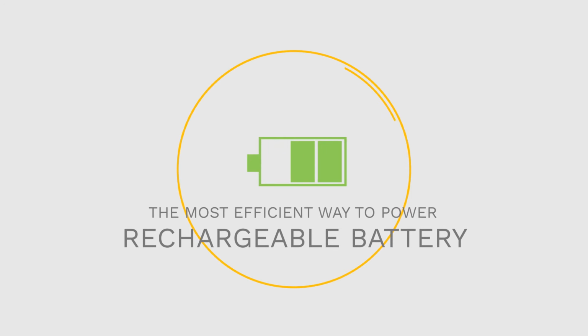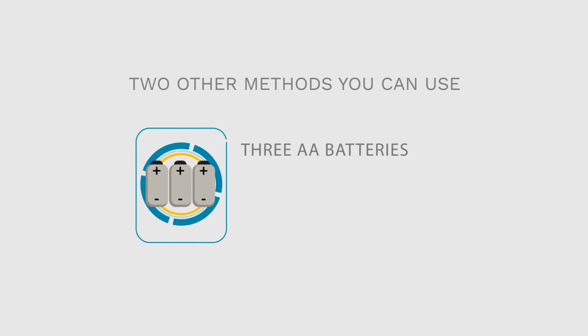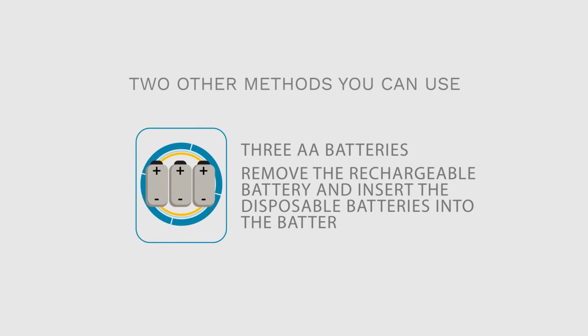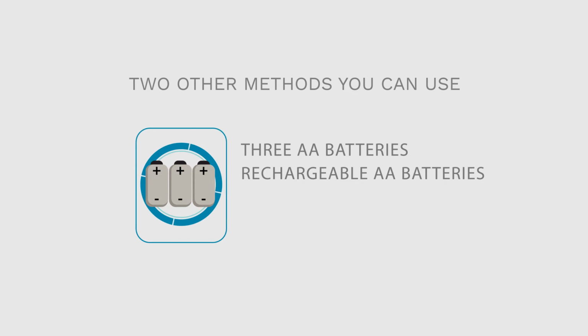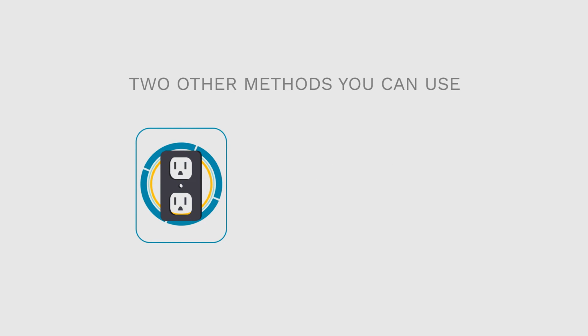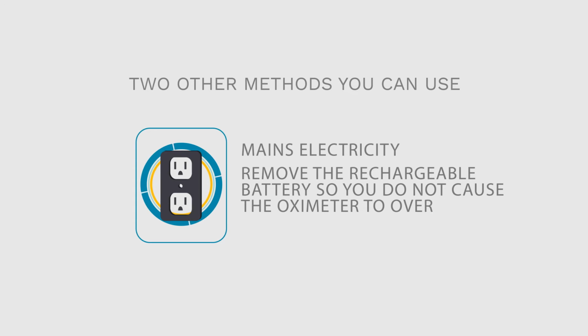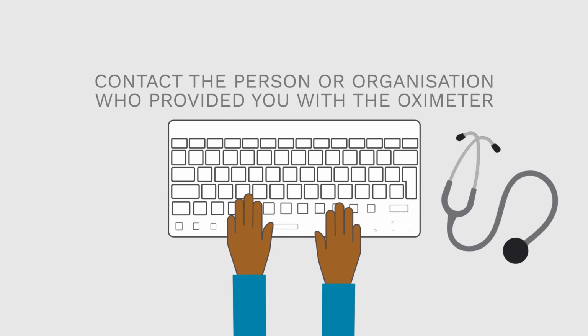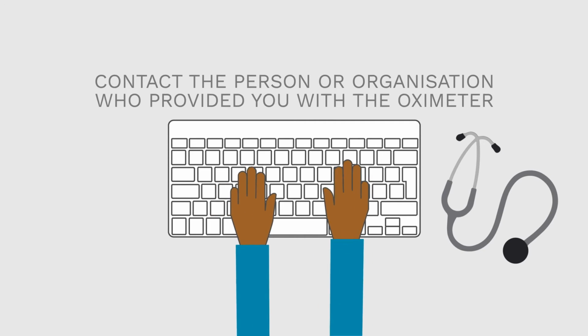The rechargeable battery is the most efficient way to power your oximeter, but if you have an emergency, don't forget that there are 2 other methods you can use. 3 normal alkaline size AA batteries. Remove the rechargeable battery and insert the disposable batteries into the battery case. Just make sure that the plus and minus points are facing the right direction. You can use rechargeable AA batteries in the same way. You can also use the oximeter directly from the mains electricity. If you're going to use this method on a long-term basis, remove the rechargeable battery so that you do not cause the oximeter to overheat. If your rechargeable battery stops working, contact the person or organization who provided you with the oximeter, or contact Lifebox directly.